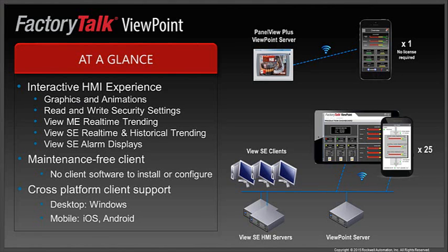Now, to summarize the main points about FactoryTalk Viewpoint, it can provide a truly interactive web-based HMI experience without requiring any additional development. There is full support for graphics and configured animations. Security can be configured to provide users with read-write access. There is real-time trending for both View ME and SE, with historical trending and alarm displays for View SE. It is a maintenance-free client, which means there's no browser software to install or configure. And with HTML5 rendering, we have support for Windows, iOS, and Android.